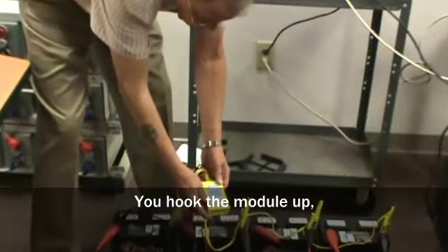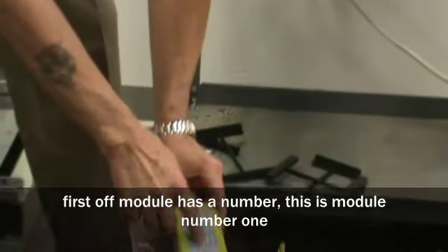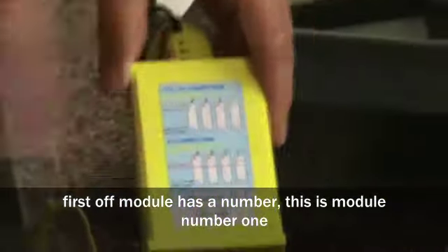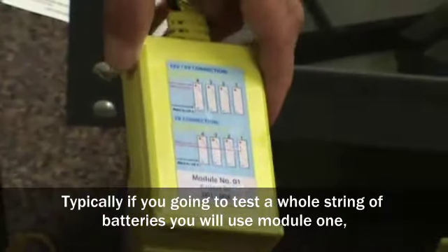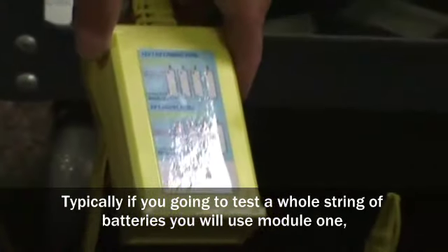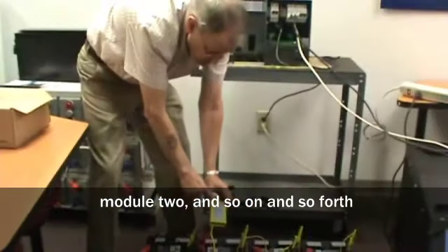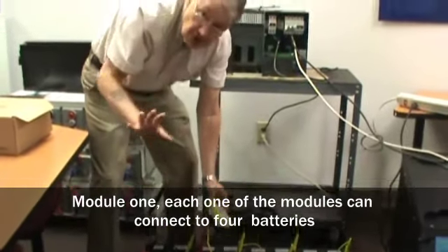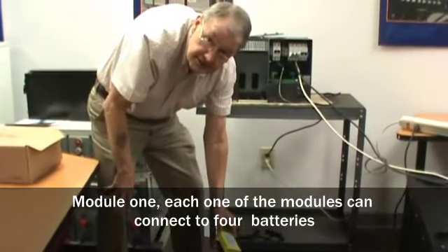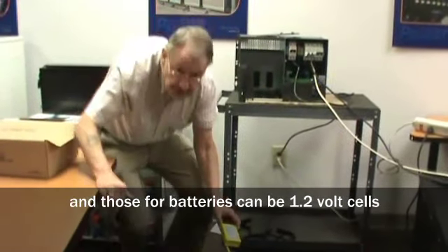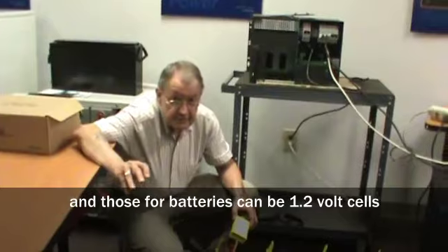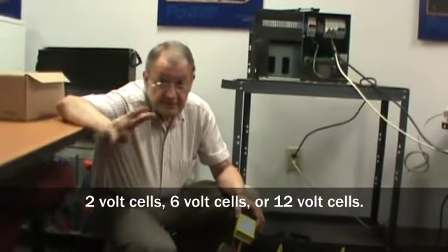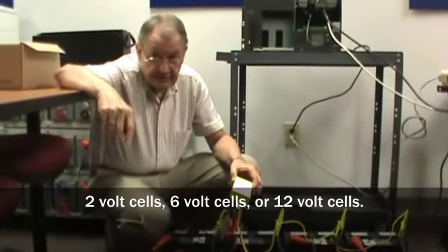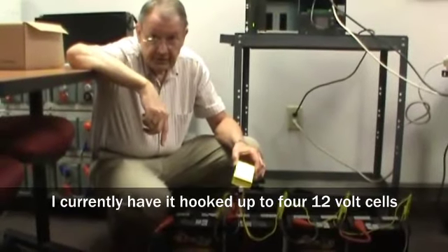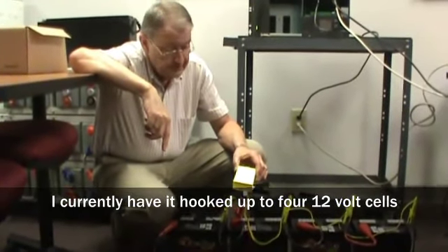When you hook the module up, first off, the module has a number. This is module number 1. Typically, if you're going to test a whole string of batteries, you'd use module 1, then module 2, and so on and so forth. Each one of the modules can connect to 4 batteries. And those 4 batteries can be 1.2 volt cells, 2 volt cells, 6 volt cells, or 12 volt cells. I've currently got it hooked up to 4 12 volt cells.